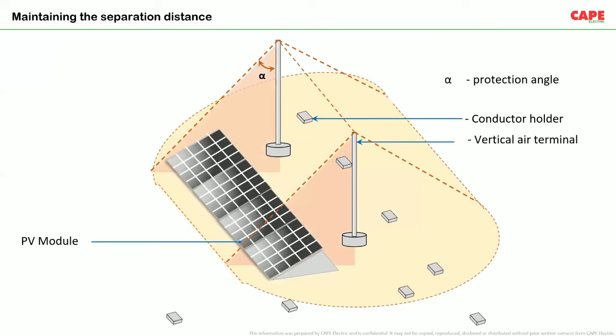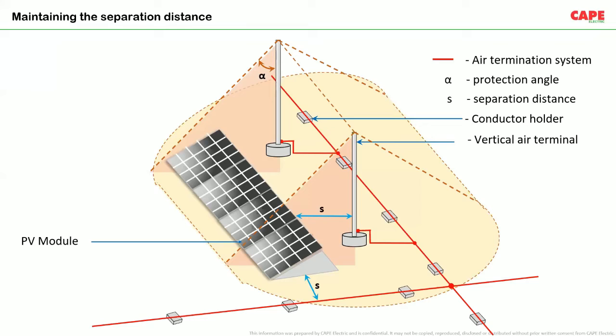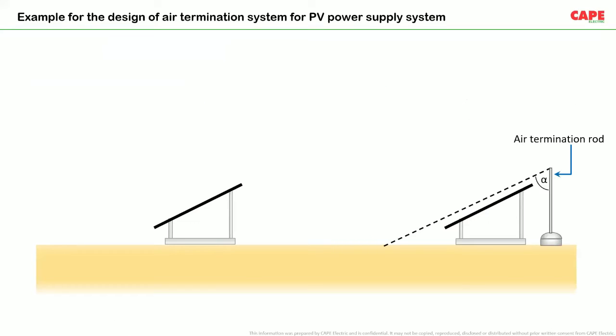Two techniques are applied. One is electrical separation. Electrical separation means the lightning protection system is away from the solar PV module. That means there is no arc over or flash over from the lightning protection system to the PV at the time of lightning, because the separation distance is calculated and maintained here. The rod is away from the PV module. The conductor is away from the PV module. This is one technique.